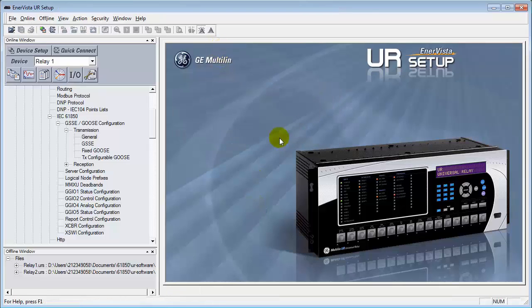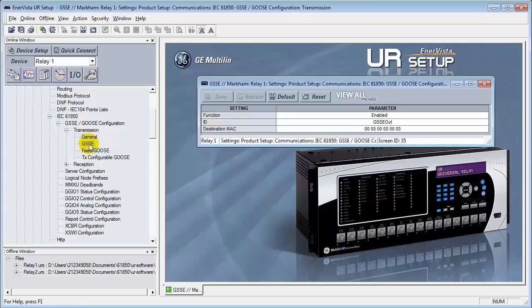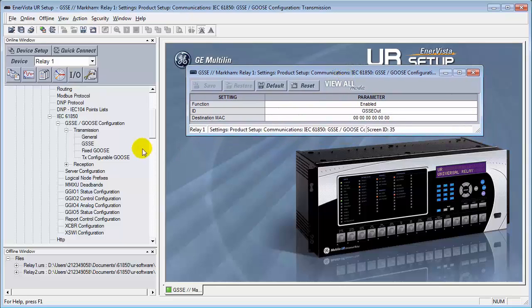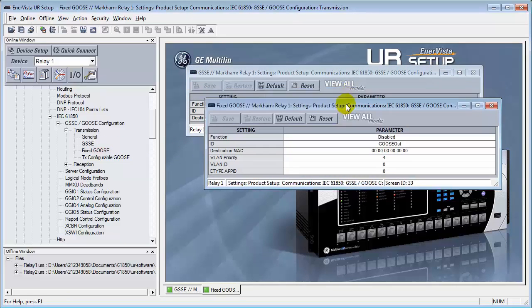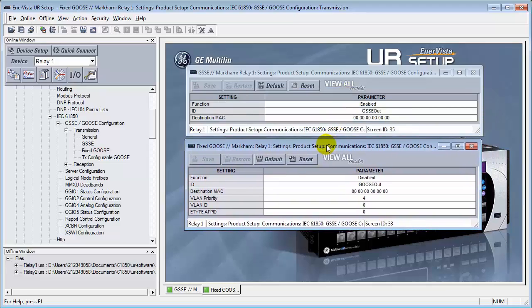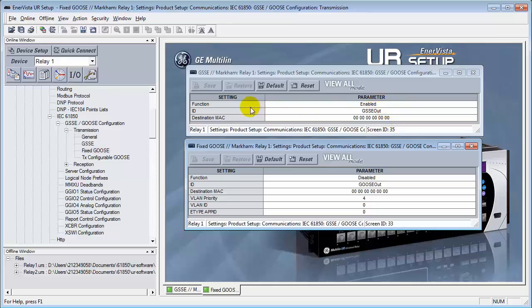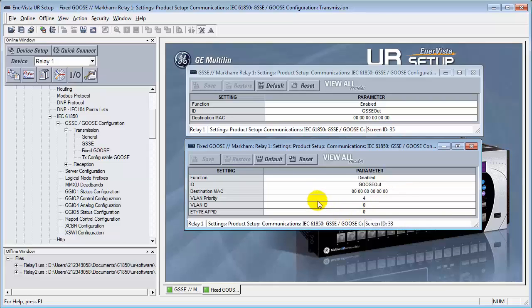Let's close that. The next thing, we have two types of gooses here. We have GSSE and fixed goose. These two are very similar in nature. Let me just open them both up. What's important here is this. They will not both operate at the same time. They will conflict with each other. So when we're doing this manually, one of the things that we have to do is disable the GSSE. You can see they're very similar in appearance. There's a function ID, destination MAC. The fixed goose has a couple of other security features built into it. VLAN priority, VLAN ID, E-type application ID.